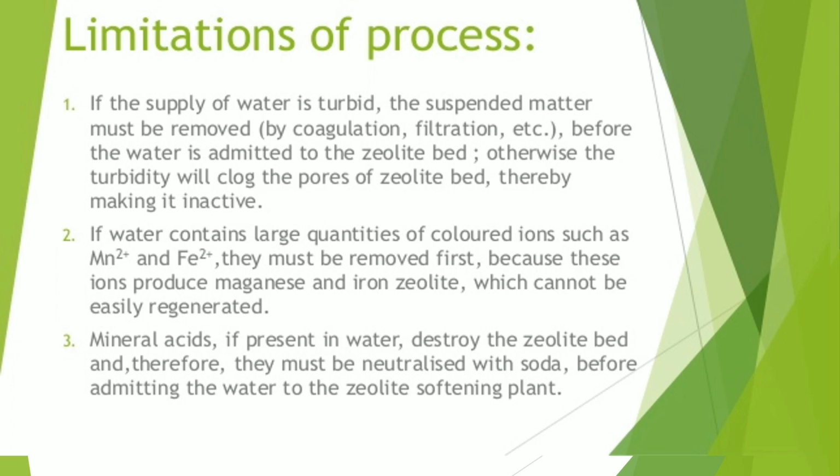The next limitation is that if the water contains a large quantity of manganese and ferrous ions, they must be removed first because these ions produce manganese and iron zeolites, which are very difficult to regenerate. The next limitation is that if mineral acid is present in water, it must be neutralized with soda, otherwise it destroys the zeolite bed. And the water to be softened should not be hot, as the zeolite tends to dissolve in it.